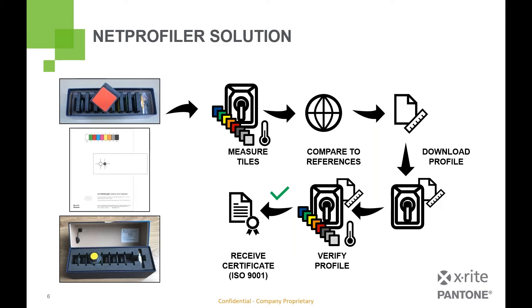NetProfiler is a rather easy solution run at your facility. It encompasses a number of different types of standards depending on the instrument, and these standards are read through the spectrophotometer. Those readings are then compared to the master that was read of each of these tiles. These are synced back to the instrument after being run through the NetProfiler algorithm, where they're then verified again by rereading these tiles on your spectrophotometer to verify that the profile being pushed back to the device is providing the correction that was expected. From there you'll receive a certification which gives you ISO 9001 compliance if that's written into your standard.